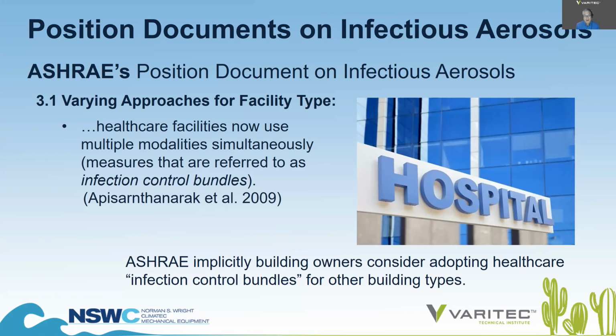What do I mean by that? Well, we'll explore it in greater detail shortly, but why not use ultraviolet lighting or enhanced filtration? Why not use more ventilation air if your HVAC system can handle that? Why don't you use a blended approach? Because there's no absolute cure-all to prevent the risk of transmission. But the more safety nets you put in place, the less chance of transmission can occur within that building. That's the way I take ASHRAE's direction in their position document.